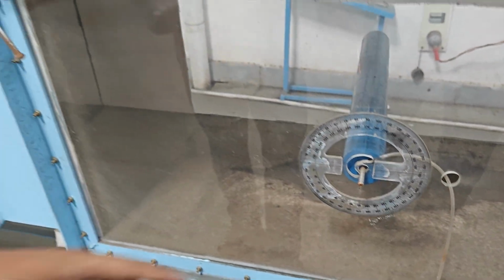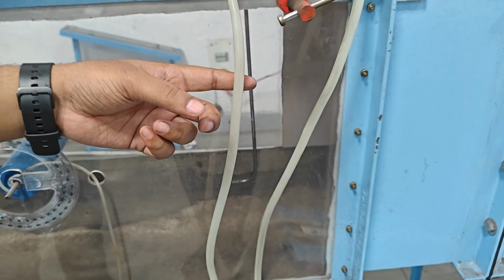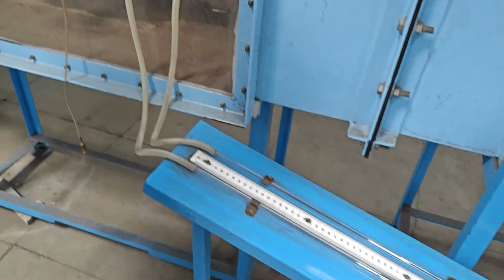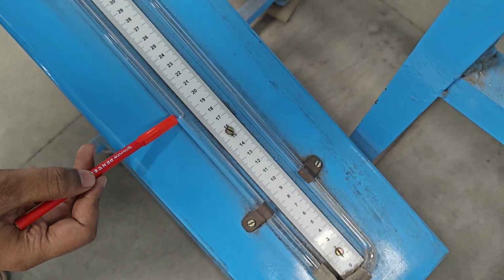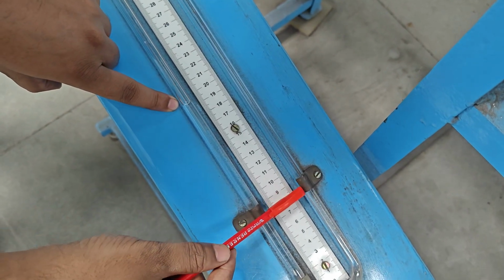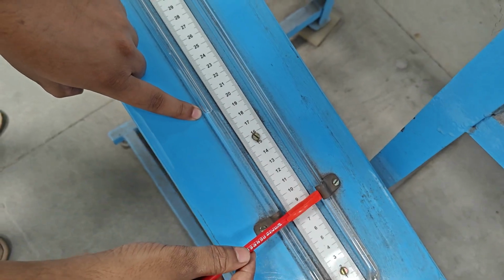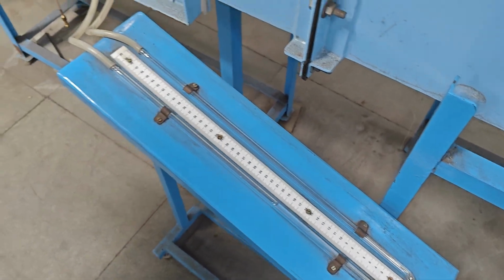These are the bodies, and this is the pitot tube. The pitot tube is connected with both the stagnation and static points, and we are getting this difference. Here is H1, this one is your H1, and here it is H2. So this delta H of water we put in the formula derived from Bernoulli's equation. And this is the ID fan section.